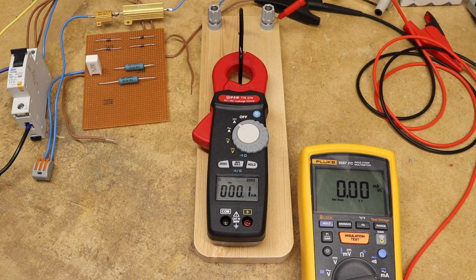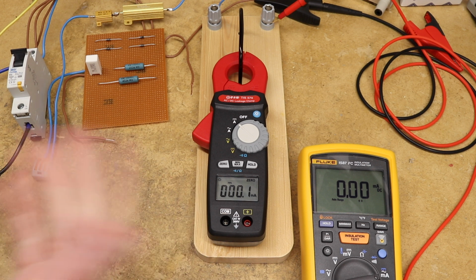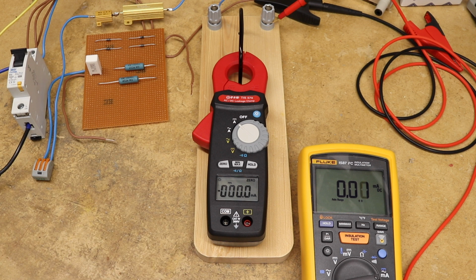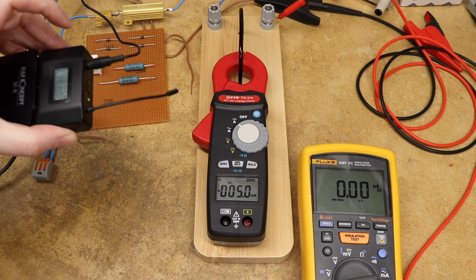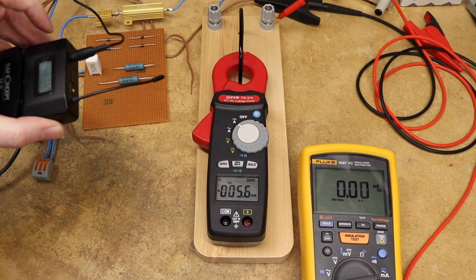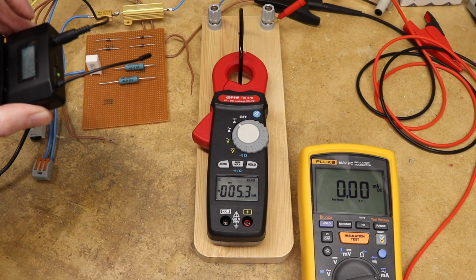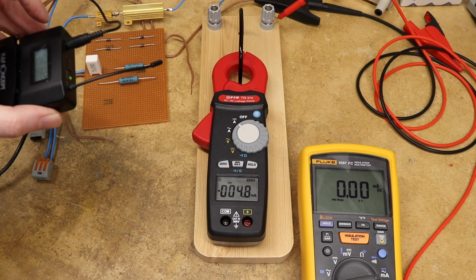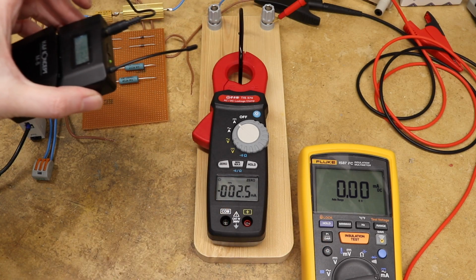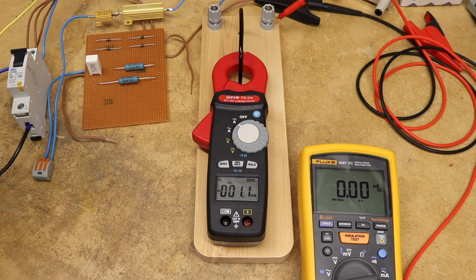The only thing to be slightly wary of is that this does appear to be very susceptible to radio interference. You can see I'm all switched off and we're back down to zero. If I grab my wireless mic and bring it in closer, you can see what happens to the reading. That's just radio interference, so it's worth being aware of if you get an erratic reading. It's not affecting my Fluke, but it's affecting the current clamp here. That did have me confused for a while till we resolved it.